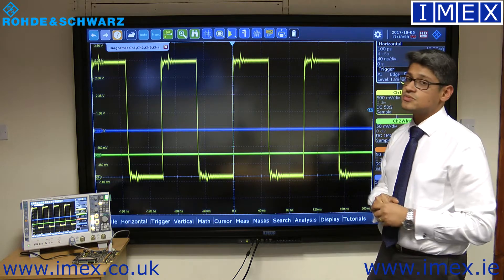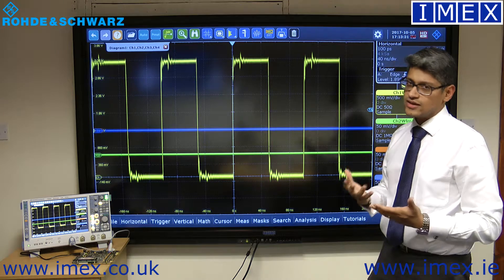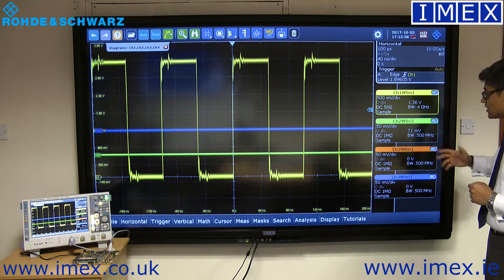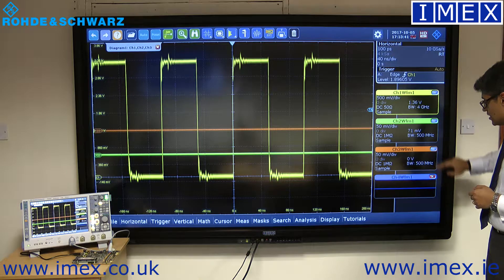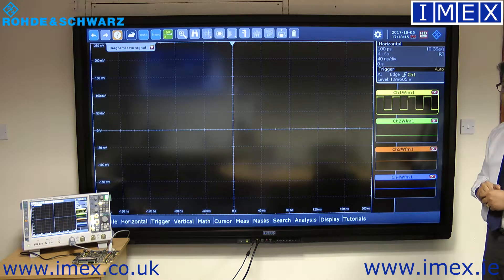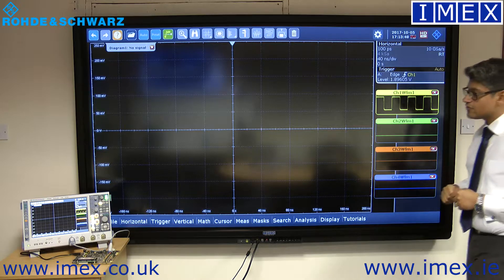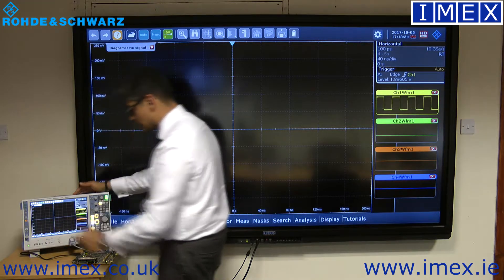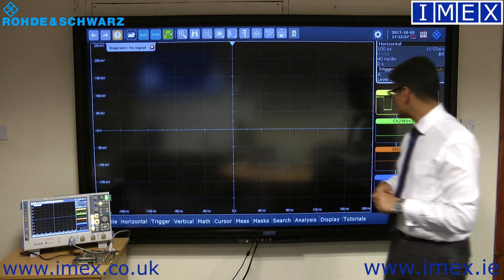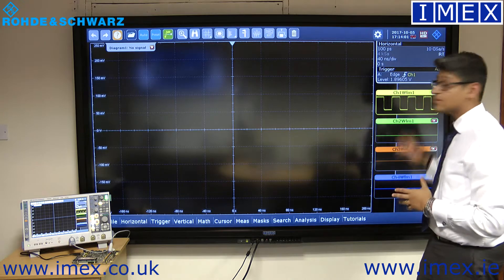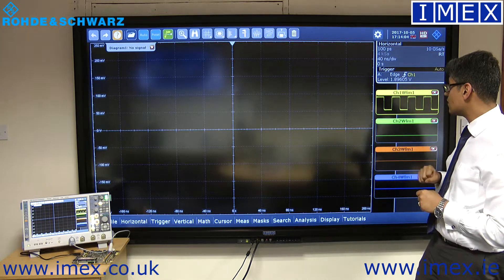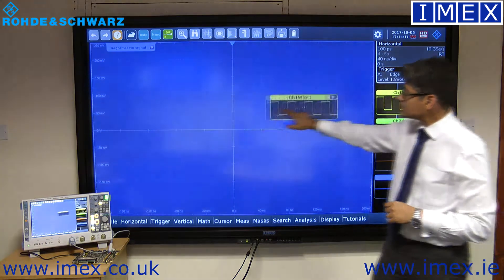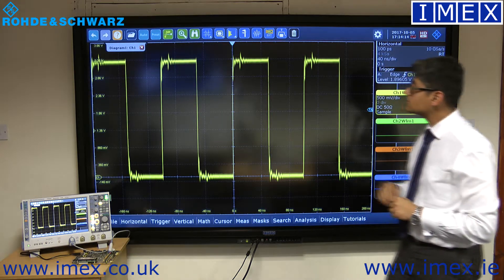With multiple channels and measurements on screen, things can get hard to read. For this reason there's a minimize icon — for example, if you have a trigger channel you rarely want to see, you can minimize it and it moves to the side. This is a live waveform — if you take the probe out it goes off, put it back and it returns. It's not a JPEG or a preview; it captures data every single time. To restore a channel, just drag it back onto the main screen.